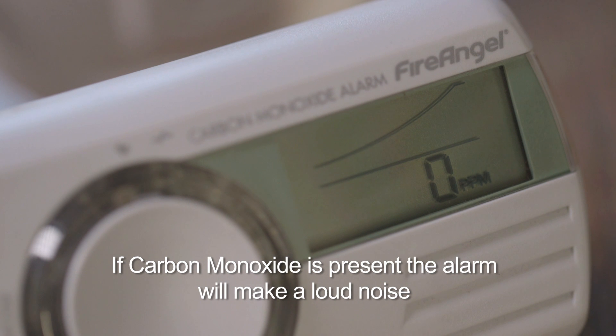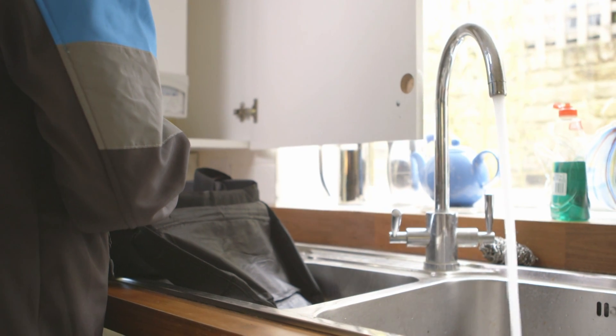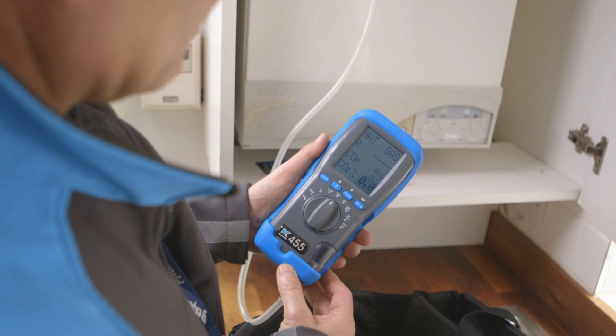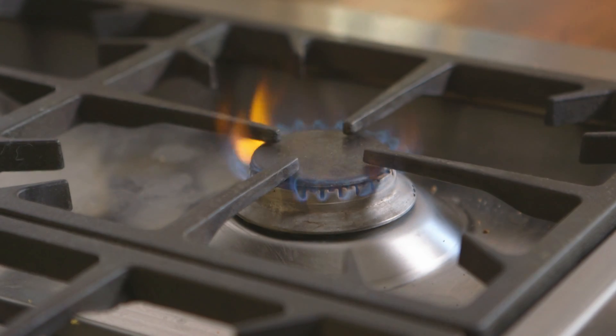When we come to the service of the boiler, we're looking for visual indications of potential carbon monoxide, which will be staining around the appliance, discolouration, distress. On an appliance where we can see the flame, we're looking for a nice bright blue flame, a little bit of orange tipping. We're not looking for a flame that's very yellow, luminous like a candle. That would be incorrect.